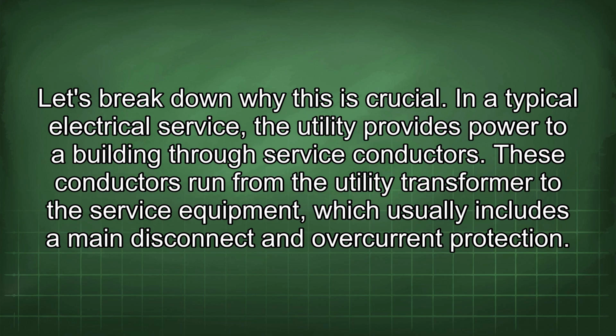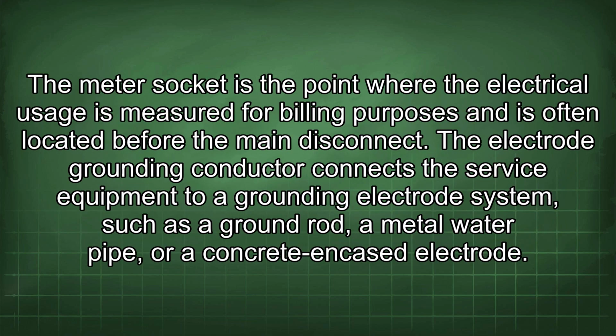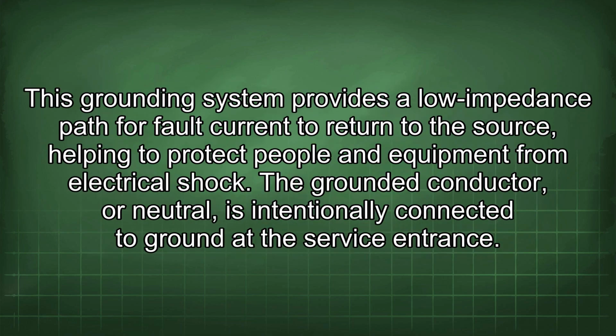In a typical electrical service, the utility provides power to a building through service conductors. These conductors run from the utility transformer to the service equipment, which usually includes a main disconnect and overcurrent protection. The meter socket is the point where the electrical usage is measured for billing purposes and is often located before the main disconnect. The electrode grounding conductor connects the service equipment to a grounding electrode system, such as a ground rod, a metal water pipe, or a concrete encased electrode. This grounding system provides a low impedance path for fault current to return to the source, helping to protect people and equipment from electrical shock.